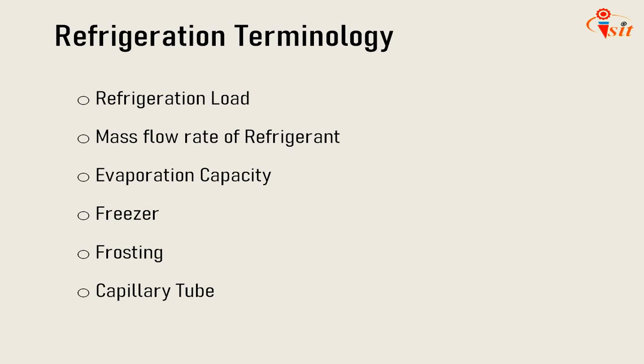The second terminology is Mass Flow Rate of Refrigerant. The refrigeration capacity of a system decides the mass flow rate of refrigerant when working under specified conditions. Mass flow rate of refrigerant is the ratio of refrigeration capacity to the refrigerating effect per kg of refrigerant.